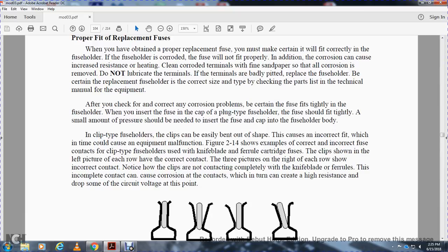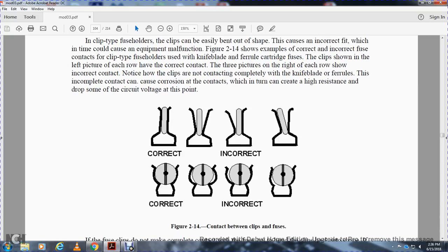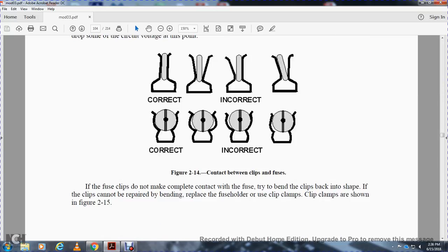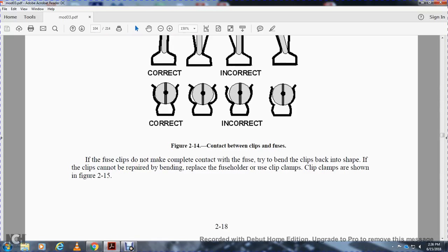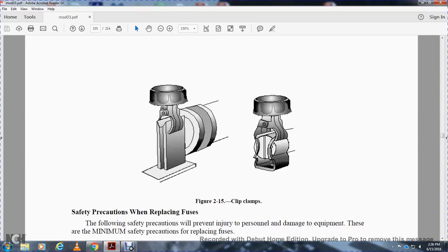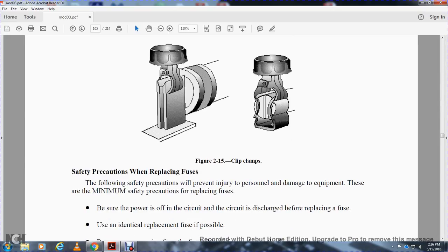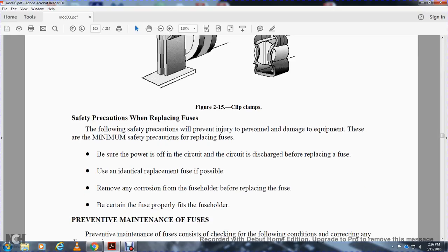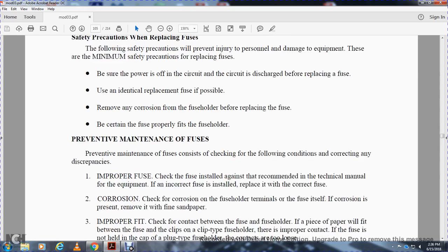Ferrule cartridge fuse contacts: the clips shown on the left side each have correct contact. The three pictures on the right side show incorrect contact - notice how the clips are not making complete contact with the knife-blade and ferrules. This incomplete contact causes high resistance and drops some of the circuit voltage at that point. Correct, incorrect, incorrect, incorrect. For fuses with clips that do not make contact, try to bend the clips back into shape. If the clips cannot be repaired by bending, replace the fuse holder. Clip clamps are shown in Figure 2-15. Safety precautions when replacing fuses: the following precautions will prevent injuries and damage to equipment. Minimum safety precautions when replacing fuses: be sure the power is off in the circuit before replacing the fuse. Use only identical replacement fuses. Remove any corrosion from the fuse holder before replacing the fuse. Be certain the fuse fits properly in the fuse holder.